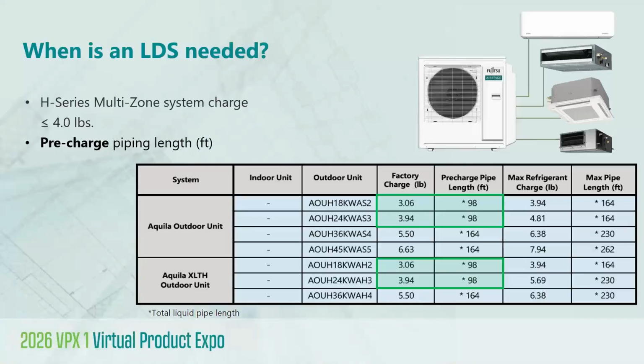You've probably been wondering about this, so let's talk about it: what about multi-zone systems? We covered single zone, but what about multi-zone? The good news is that many of our smaller capacity multi-zone systems still fall within that 4 pound threshold, again at least up to the factory pre-charge piping length. What makes this convenient is that both the single zone and multi-zone tables give you a quick at-a-glance way to confirm standard compliance. You can easily check both the pre-charge piping limits and the maximum piping length allowances without having to do any piping calculations for in between.